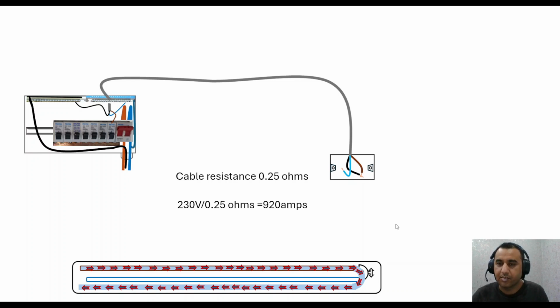And because there isn't resistance, such as we had with the microwave appliance there, this cable has very low resistance. Between this line and the earth CPC conductor, we got resistance of roughly 0.25. That doesn't include the appliance, because it's just happened before the appliance.